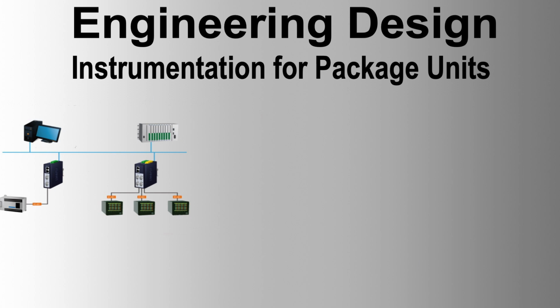Functional, performance and interface test. The vendor shall prepare a FAT procedure and schedule for the contractor and principal's approval. The purpose of this FAT is to demonstrate with a total system functional test that the operation of the control, monitoring, IPF, and logic systems included in the equipment package perform as specified in the requisition. The functional test shall include the communication link to the plant DCS. The vendor shall provide the necessary equipment to demonstrate the full functionality of the communication links.